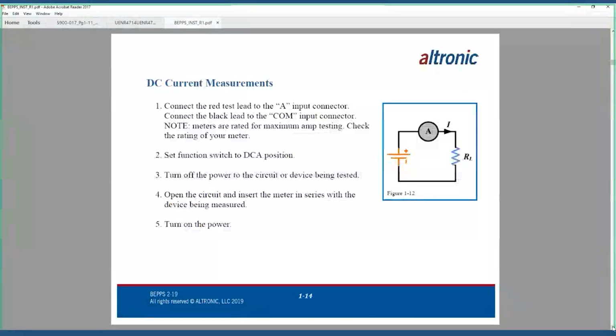So on a DC current, we connect the red test lead on the meter to the A input, which stands for amperage. We connect the black lead to the common so it doesn't move. And don't forget to check: have an idea what you should see for amperage on your circuit, and make sure that your meter's rated for high enough amp flow through it for testing so you don't blow up your meter. Most meters have a 10 amp rating, but some are less.